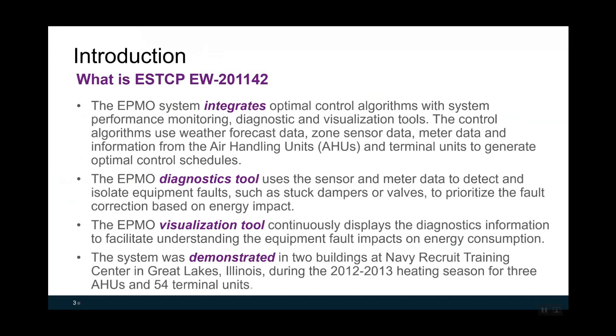The EPMO diagnostic tools use the sensor and meter data to detect and isolate equipment faults such as stuck dampers, and to prioritize fault correction based on energy impact. The third key feature is that the EPMO visualization tool continuously displays diagnosed information to facilitate understanding of equipment fault impacts on energy consumption. This system was demonstrated in two buildings at Navy Recruit Training Center in Great Lakes, Illinois during the 2012-2013 heating season for three air handling units and 54 terminal units.